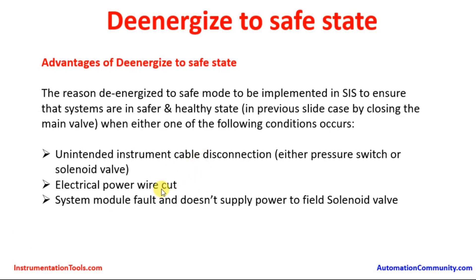Similarly for electrical power wire cut: if any power going to the solenoid valve gets disconnected due to failure of the output module — which is an electronic module — during that time also the valve has to go to the safe position, which is the fail-closed position. Similarly, if there is an instrument air failure due to a compressor trip or any blockage in the instrument airline, in those conditions also the valve has to move to the safe position to ensure that the plants are operating safely.